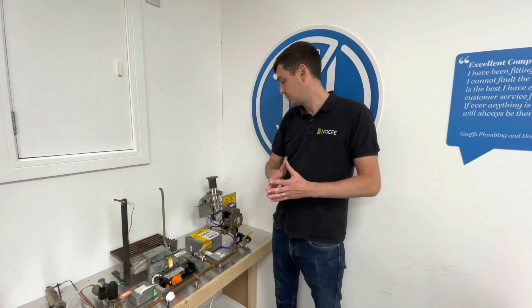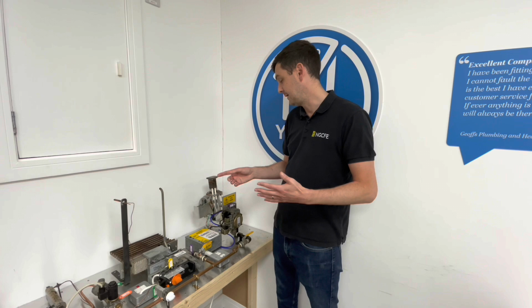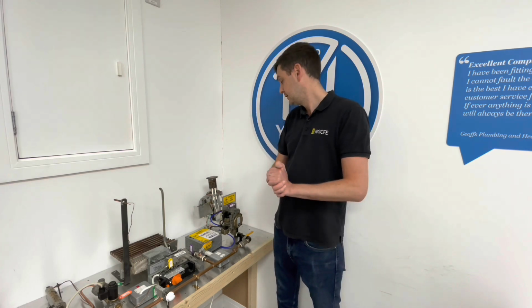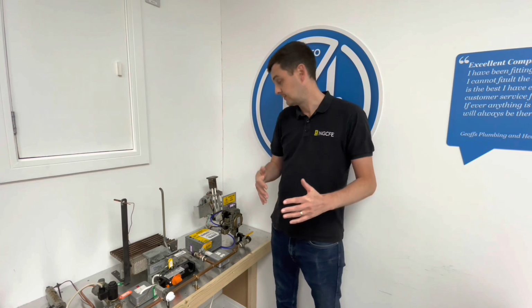So if you do have any issues, it'll generally show up on a boiler as an ionization fault or ignition fault. If it is associated with the flame rectification side, generally it's a case of the board isn't receiving the current back. So it might be that there's a break in the rectification lead, it might be that there's a fault on the board, so it's not recognising the DC current coming back. Or it could just be because there's a problem with the gas valve or the ignition probes and there's no flame being created, it's just gas being sucked and blown out the flue again. So that is flame rectification in a nutshell.